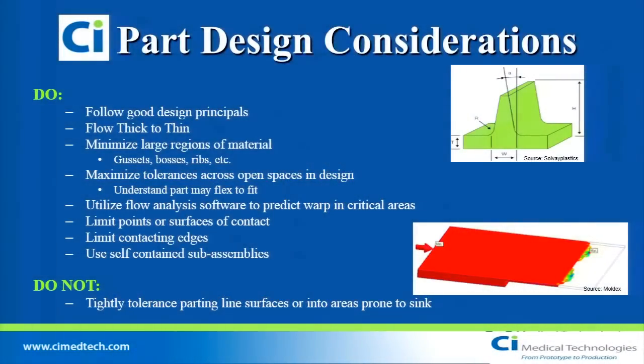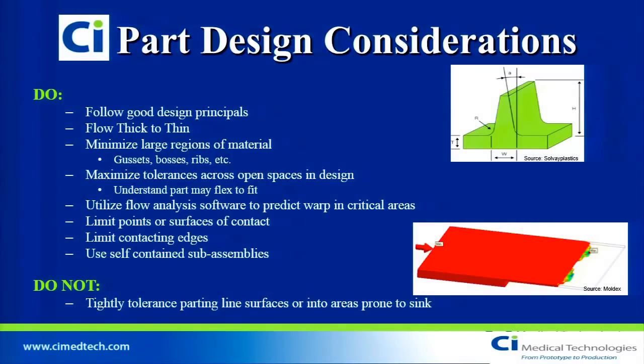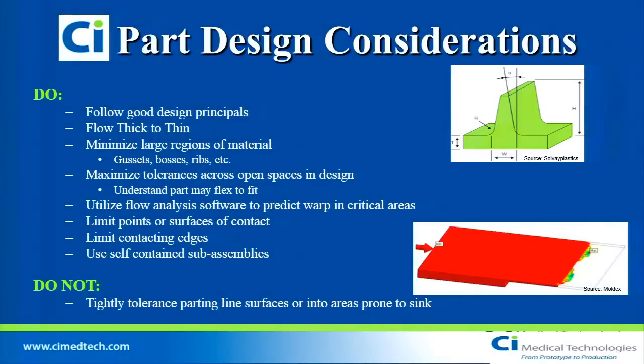Good molders will provide a lot of this information in parallel with your design. Limit points or surfaces of contact, limit contacting edges, or use self-contained sub-assemblies. Instead of fitting 50 different components into a housing or a handle, make smaller sub-assemblies and put those into the larger assembly. Do not tightly tolerance parting line surfaces or areas prone to sink.